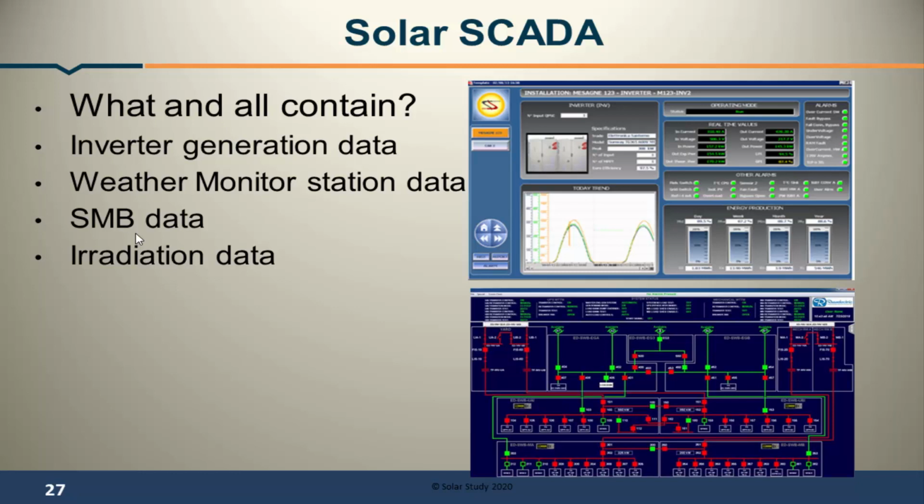Like this you will have 9 SMBs. So 5184 panels it contains. Suppose if we take 5000 into 230 watt panel, it is almost giving 1.19 megawatt. You can calculate. So that much data you will get.